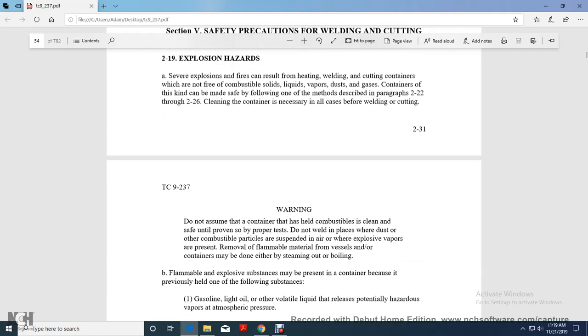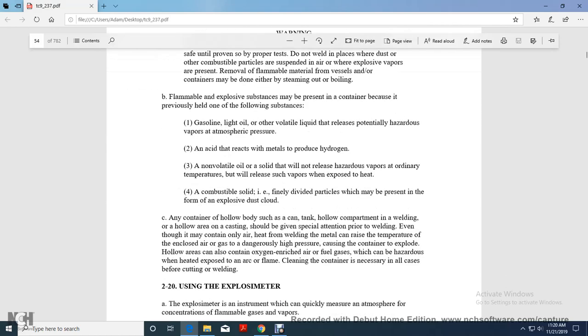When explosive vapors are present, remove the flammable material from the vessel or other container, done either by steaming out or boiling out. Flammable substances may be present in the container because it has previously held one of the following substances: gasoline, light oil, or other volatile liquid that releases potentially hazardous vapor at atmospheric pressure, and acid that reacts with the metal to produce hydrogen; a non-volatile oil or solid that will not release hazardous vapors at ordinary temperatures but will release such vapors when exposed to heat; or combustible solid, finely divided particles which may be present in the form of an explosive dust cloud.